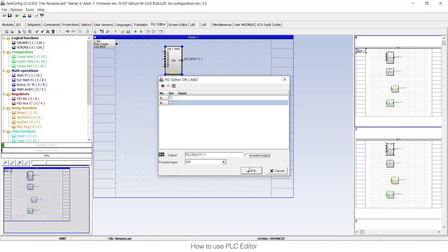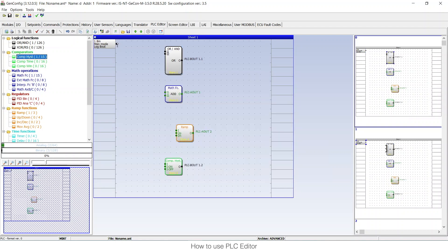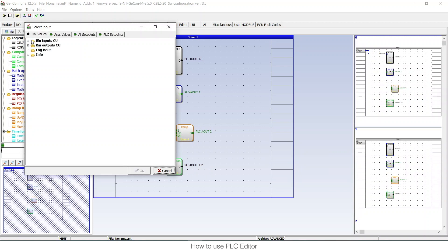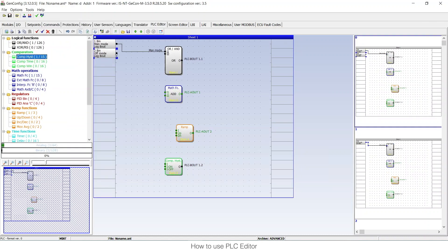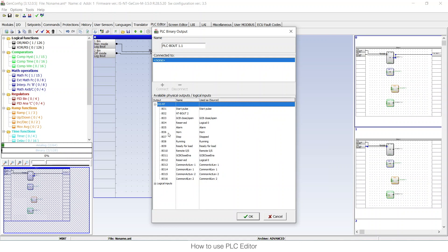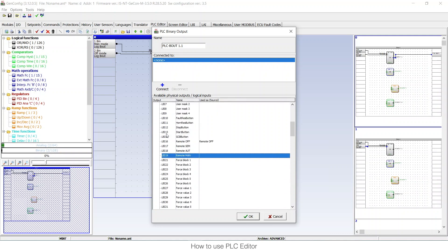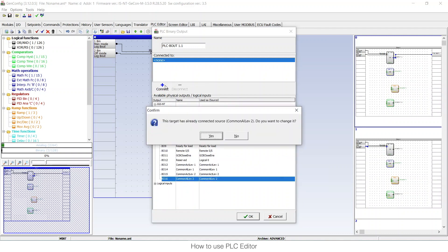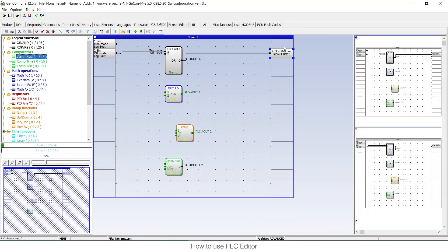Now to connect, just click and connect. I'll choose manual mode and also off mode, which means that when the controller is in manual mode or off mode the respective input will turn on. I connect the off mode here, and for the output just click and connect. The output is connected but has nothing configured yet — I can configure a physical binary output or a logic input with a pre-programmed function. I'll choose a physical binary output, press connect, then press OK, and now it's connected.